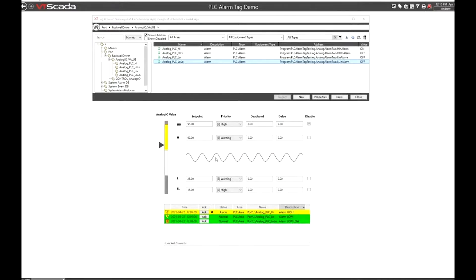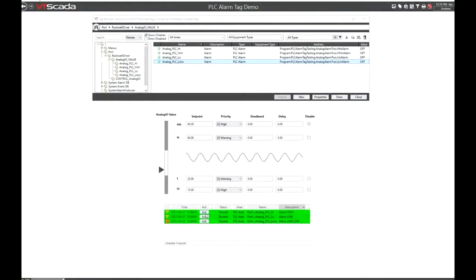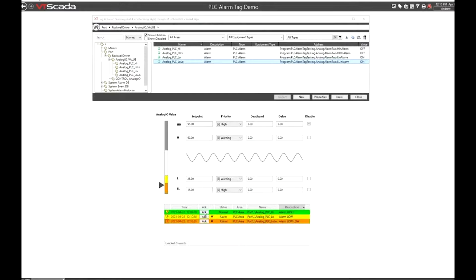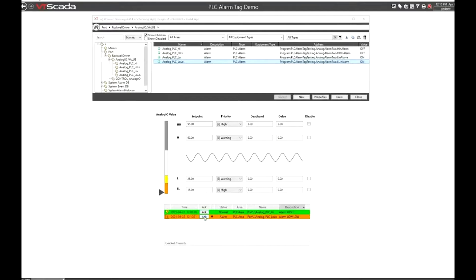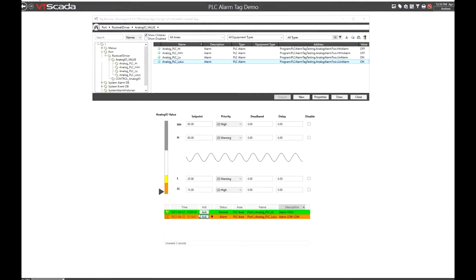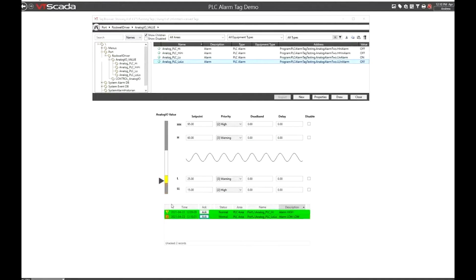This is all tapping right into our built-in alarm management system so we can see what the status of the alarm is, whether it's acknowledged, whether it's turned on, and again we can perform status updates to the alarms here. If I write an acknowledge, I've acknowledged that alarm, the ACK bit in the PLC turns on, and we read that back so we know that the PLC alarm tag has been acknowledged.